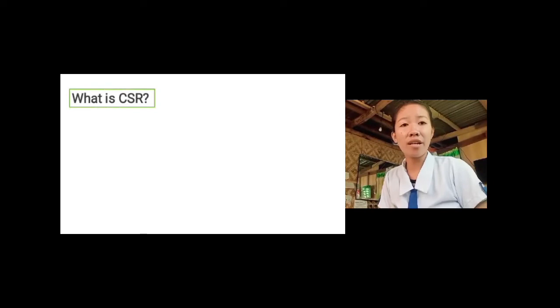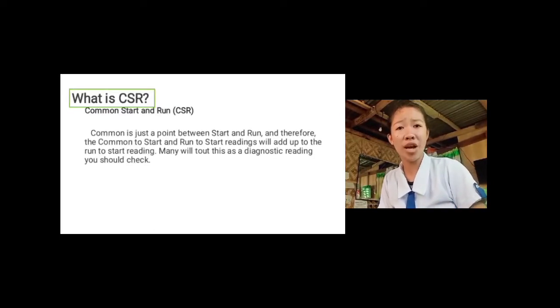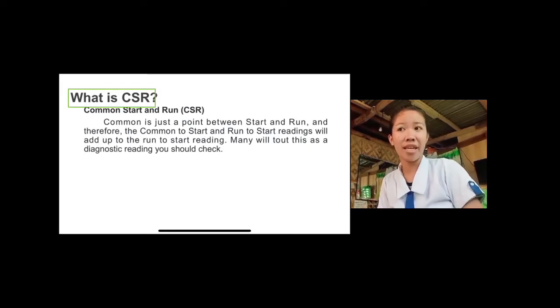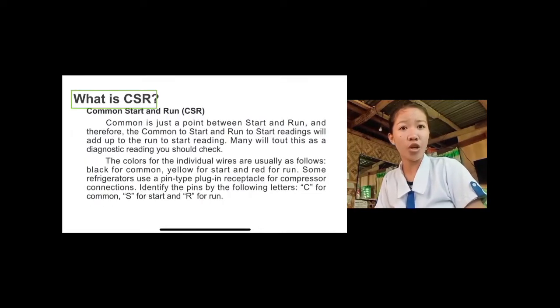So, what is CSR? As we all know, our topic is how to find the CSR, but we don't know what CSR is. CSR is the acronym of Common, Start, and Run. Common is just a point between start and run, and therefore the common to start and run to start readings will add up to the run to start reading. Many will tout this as a diagnostic reading you should check. The colors of the individual wires are usually as follows: black for common, yellow for start, and red for run.